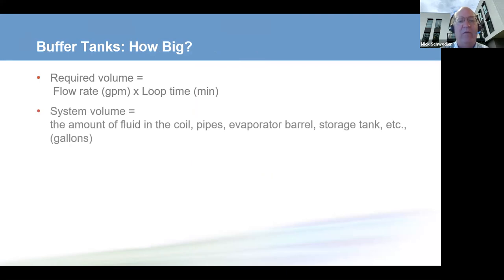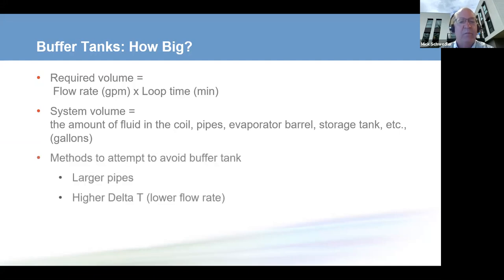So we compare that required system volume with our actual system volume. How much water is in the chiller evaporator, in that barrel, in the pipes, in the coils that are active, and in the storage tank. And if the system volume is less than the required volume, we have to find some way to mitigate that. Well, there are a couple ways to do that.